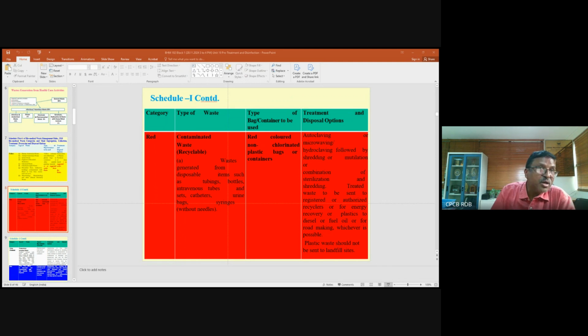Whereas with sterilization, if you adopt technologies such as autoclave, microwave or dry heat treatment, you can achieve an efficacy of about 99.9999%. Therefore, sterilization is more effective than chemical disinfectants. That is the technologies of pre-treatment of the waste. Disinfection efficacy or efficiency depends on the operational conditions and what treatment equipment you are using. What are the operating conditions that you are maintaining? Suppose you adopt the autoclave, then you have to maintain a temperature of at least 121 degrees centigrade, a pressure of 15 psi, and the treatment duration should not be less than 60 minutes.